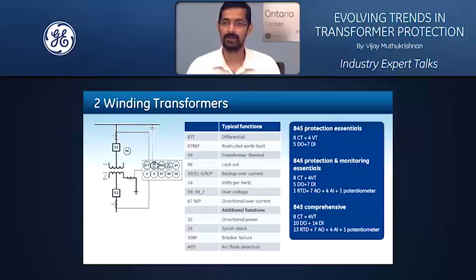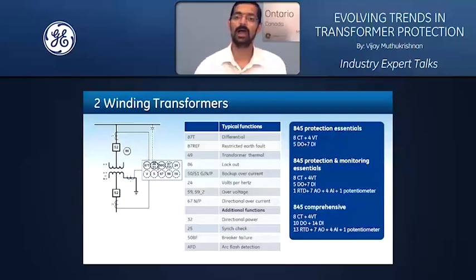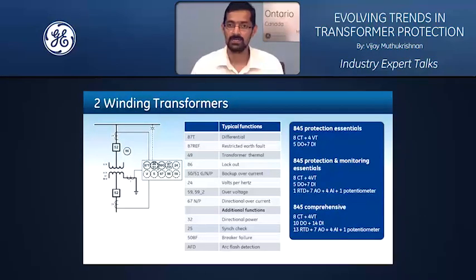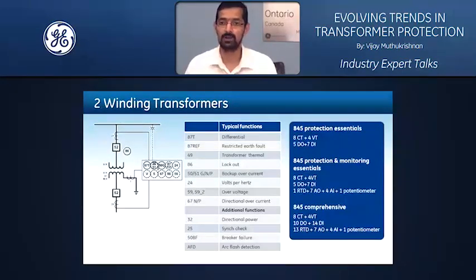Now, the power of the 845 is such that you can have a base level of monitoring added to your transformer protection by just bringing in one low voltage analog IO subsystem, or by adding a couple more RTD cards, which can allow you to have up to 13 RTDs, and two combo IO cards, scaling up your output and input requirements. You can really build a very comprehensive monitoring and even a little bit of control for your transformer in a holistic manner. That type of application is very comprehensive, and meets your protection, monitoring, diagnostics, and control requirements. That's very powerful.